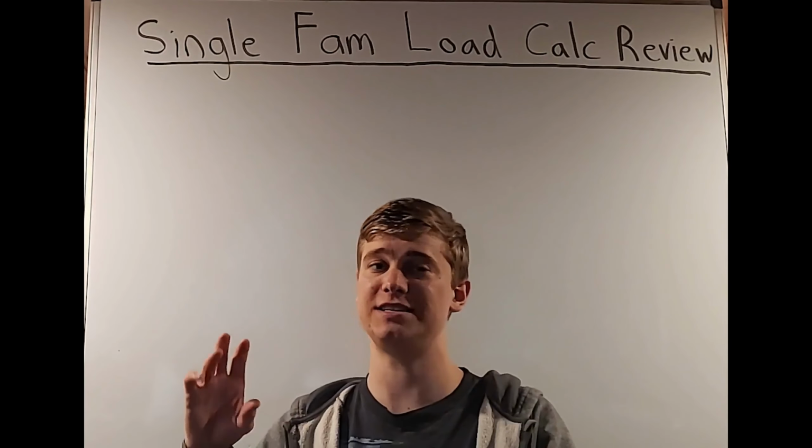And then that also doubled as me showing you how to find the minimum size overcurrent protection device and why you size up normally and how you know when to size up and when to not size up. So make sure to watch. That was the part 2 of the residential load calculation videos.